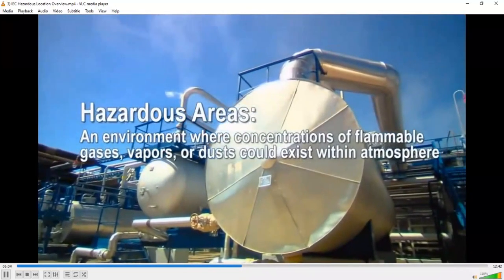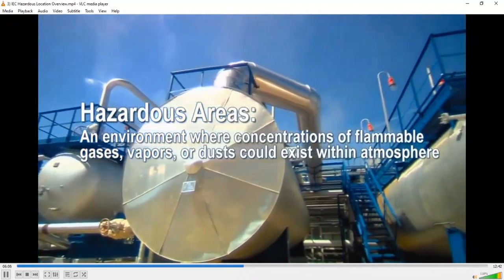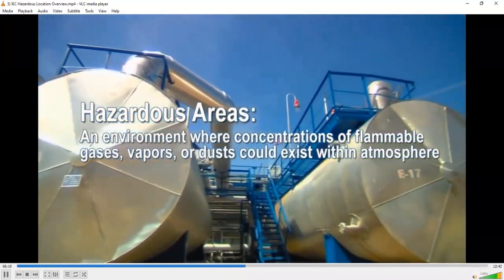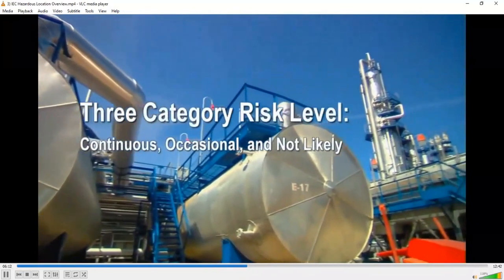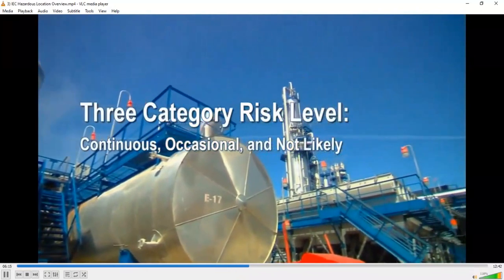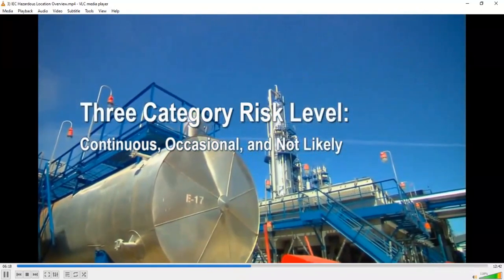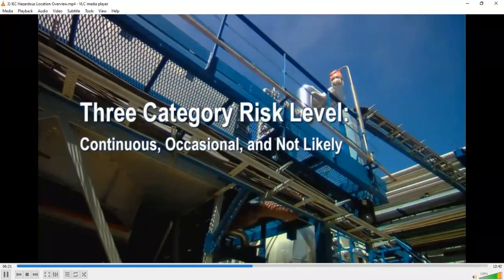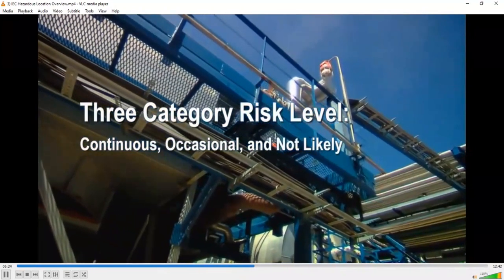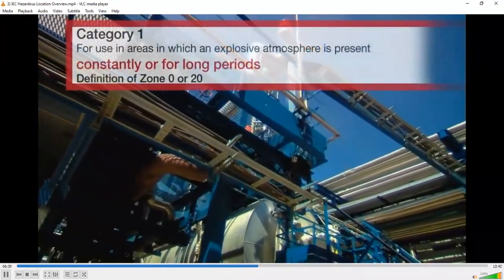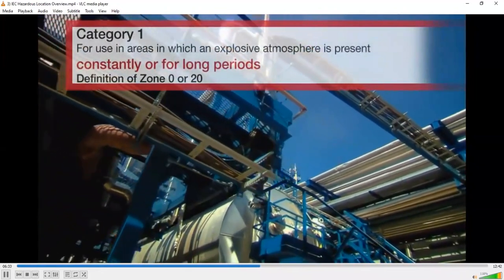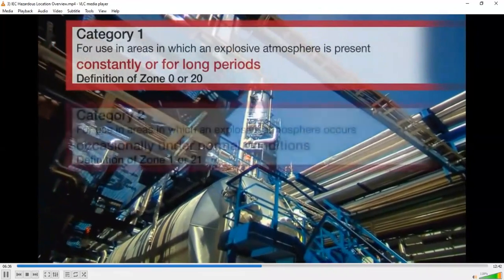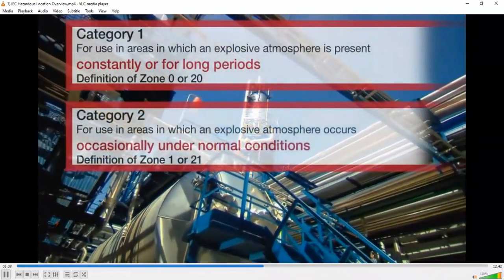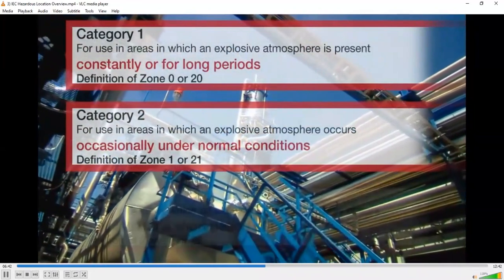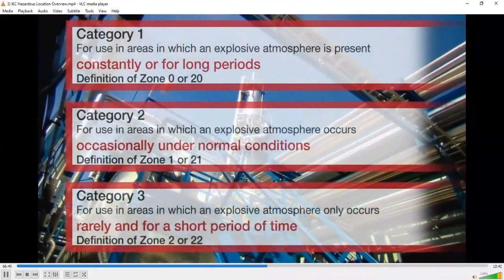As a recap, the IEC standards classify hazardous areas as environments that could contain explosive vapors, gases, and/or dust within the atmosphere. The primary categories provide the risk levels as constant, occasional, and not likely. Since elements have a variety of flammability and the physical properties could be different, IEC standards segment the types of combustible materials into zone classifications. The most hazardous is Zone 0 or Zone 20. By reducing the risk level to have occasional explosive atmospheres, the zone classification is Zone 1 or Zone 21, and further reduction of category risks would change the hazardous classification to Zone 2 or Zone 22.